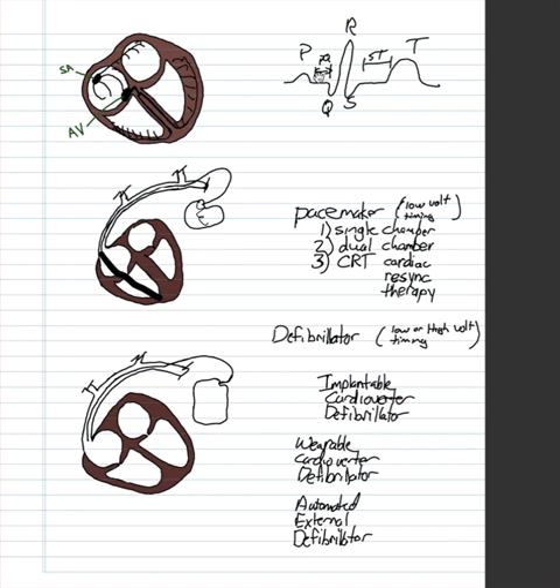The most common thing that can happen is this PQ is too long, or it sometimes doesn't happen at all. A few ways that can happen, but particularly very slow heartbeats. This is the most basic type of pacemaker, and this allows them to sense here, okay, we saw that there was a little bit of an electric pulse, we saw the P wave, they activate one of the timers that counts down from P to Q. If they don't sense the ventricles getting their release of the QRS in time, it will send a shock out.